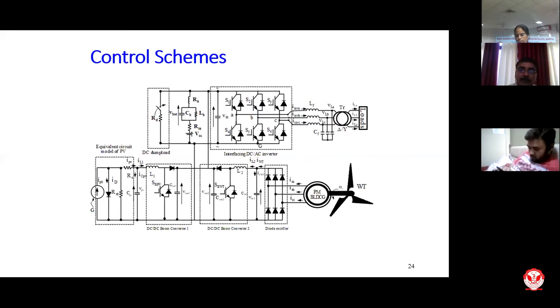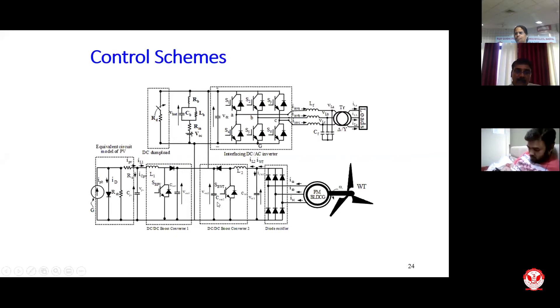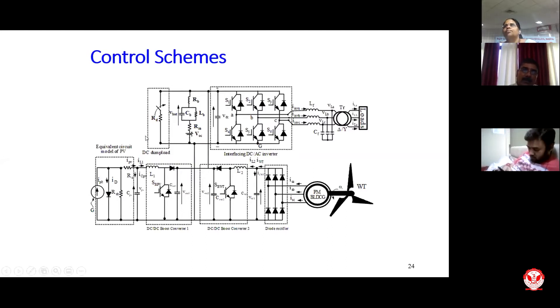One control scheme used involves power electronic converters — inverters and boost converters — because voltage levels may be low or high and must be matched to supply and load requirements. There is also a DC dump load to protect the battery. If the battery is fully charged and power is still being generated with no consumer requirement, this DC dump load absorbs the excess power. It can alternatively be used as a water heating system, as done in American and Canadian applications during winters.